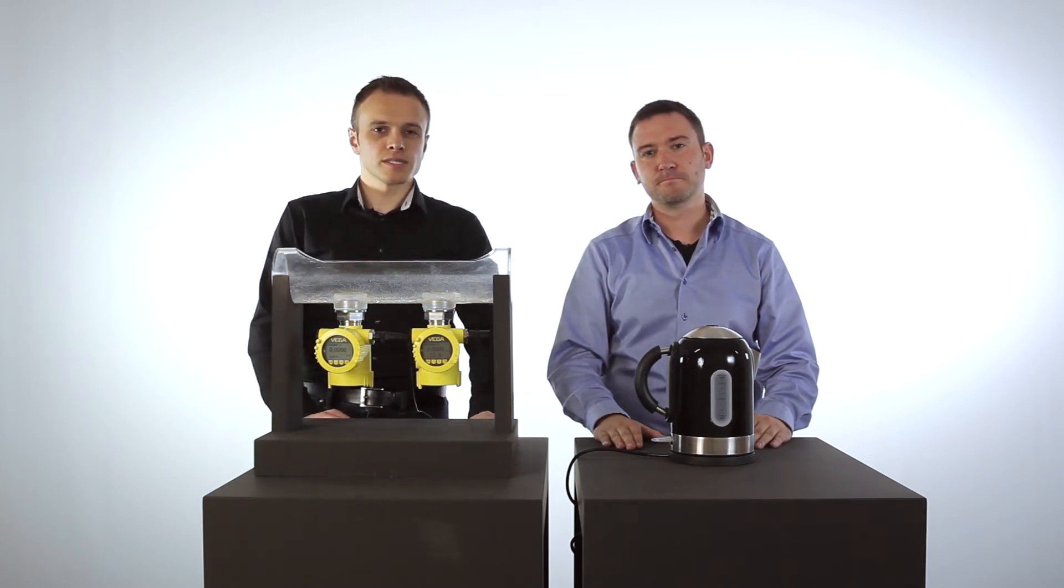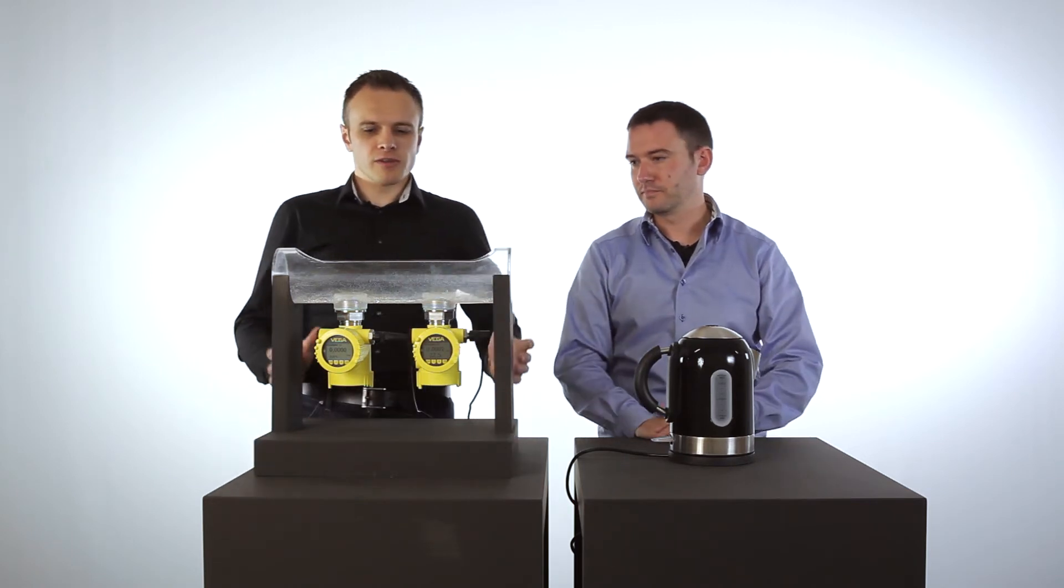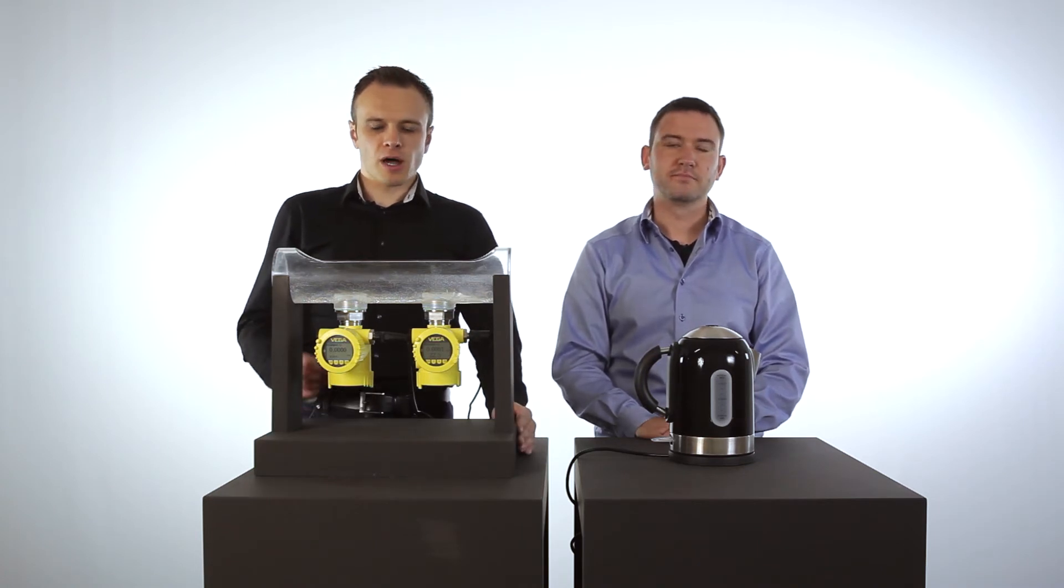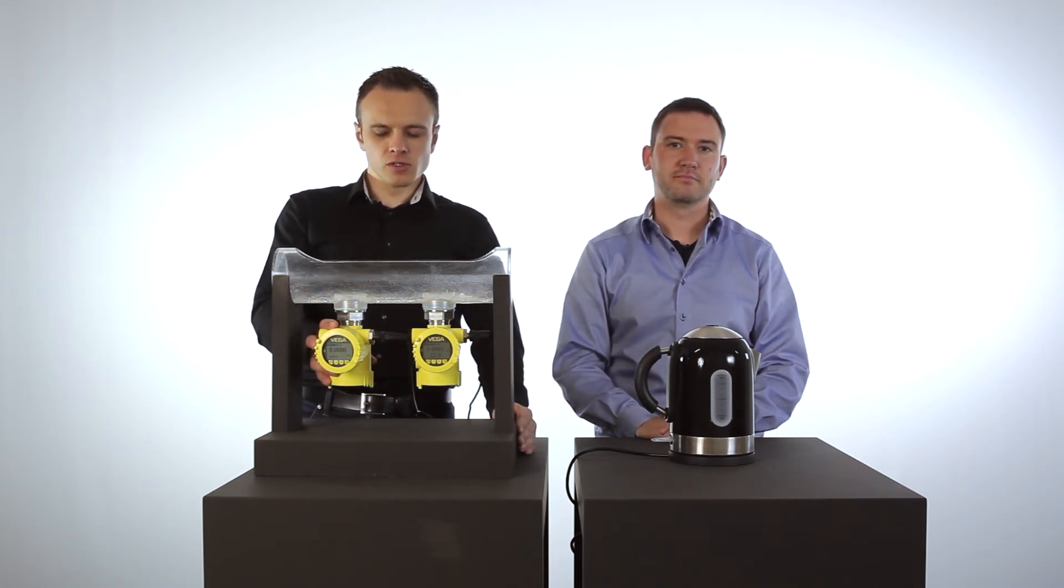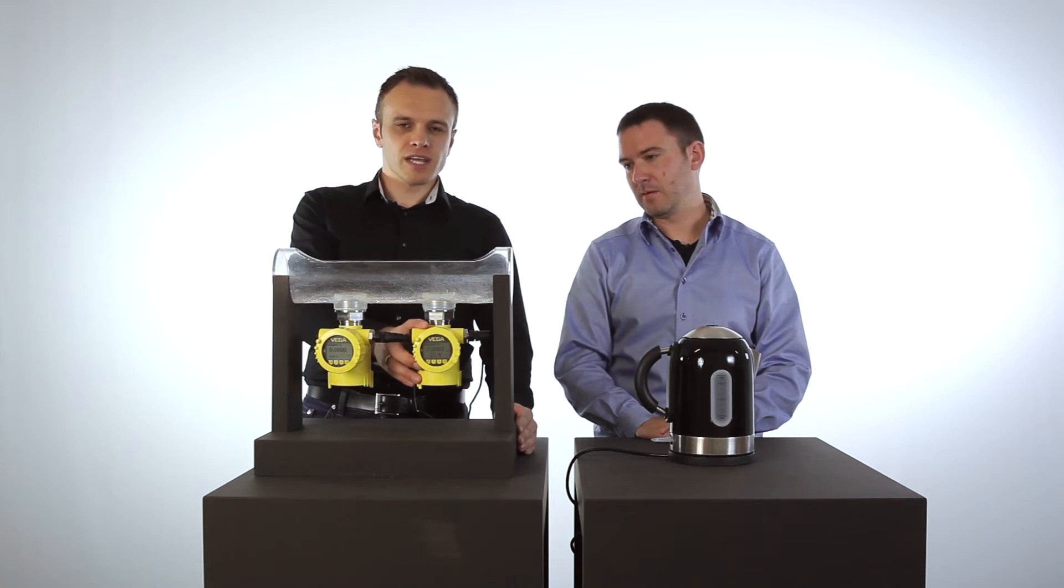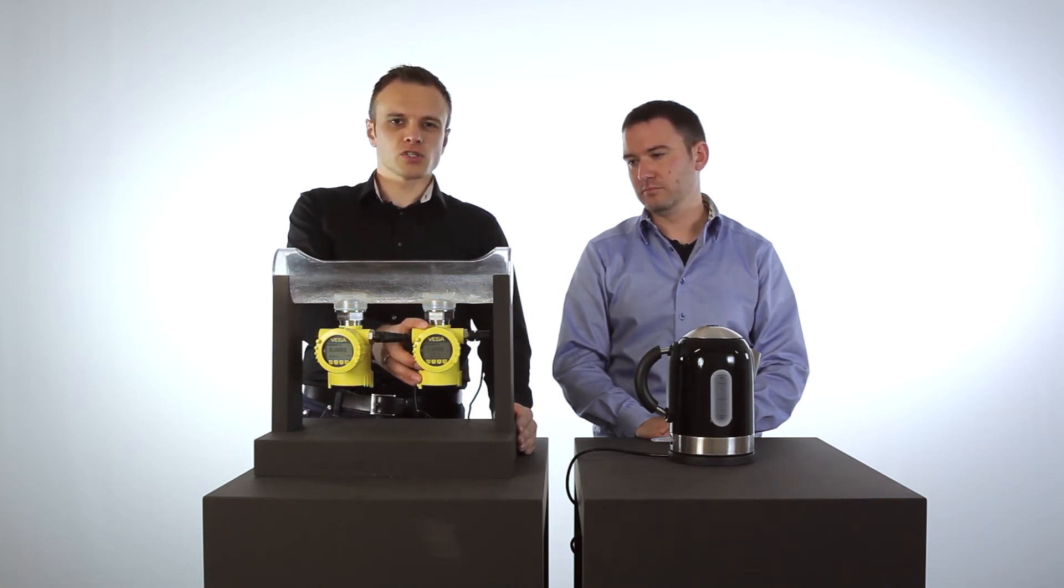To demonstrate this new technology, we have here this demonstration model. On this demonstration model, we have mounted a Vega Bar 52 with a ceramic cell without temperature shock compensation, and we also mounted a Vega Bar 82 with a ceramic cell with temperature shock compensation.